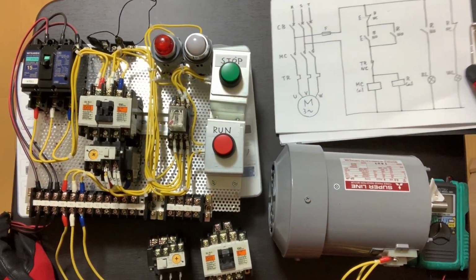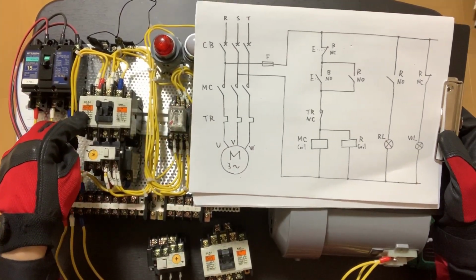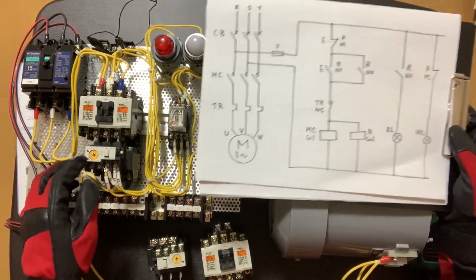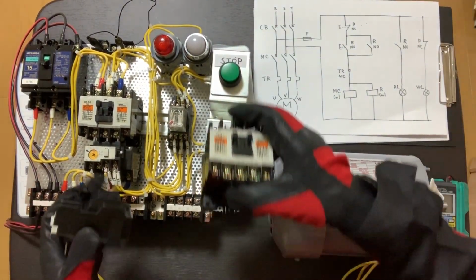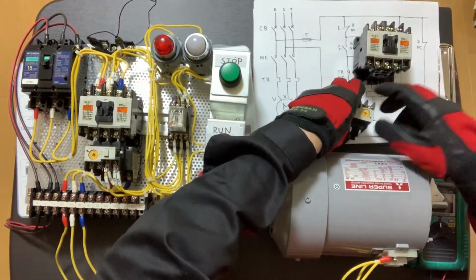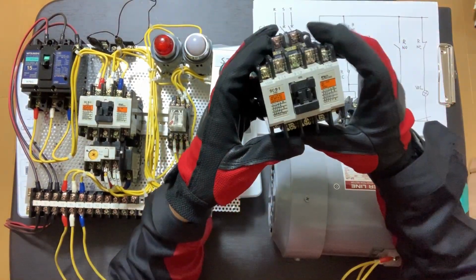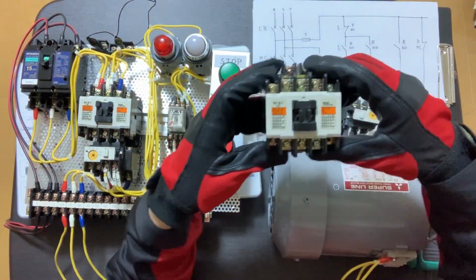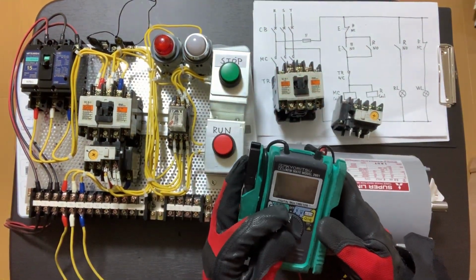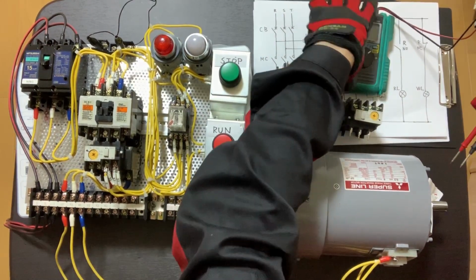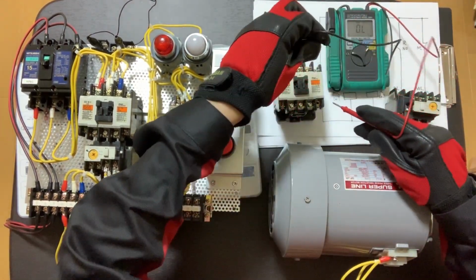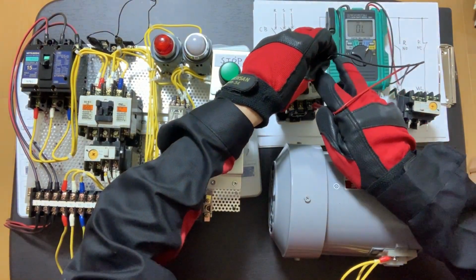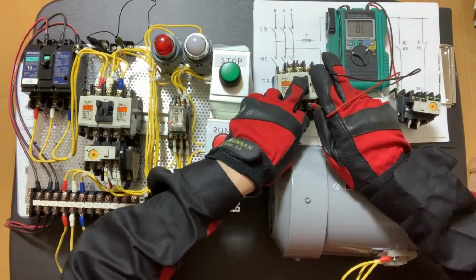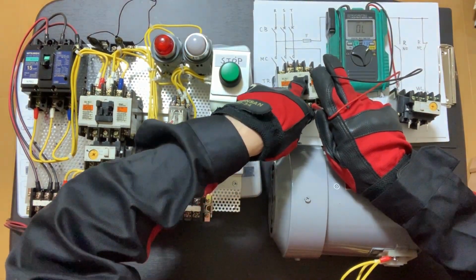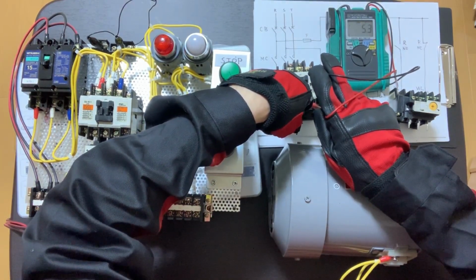The next devices are the magnetic contactor, this one, and the thermal protection relay, this one. I have the same rated ones respectively. The magnetic contactor has open and close contacts that switch with electromagnetic force. Let me explain with the actual device. This is a normally open contact, and if I push this switch, it turns to short circuit, it's closed.